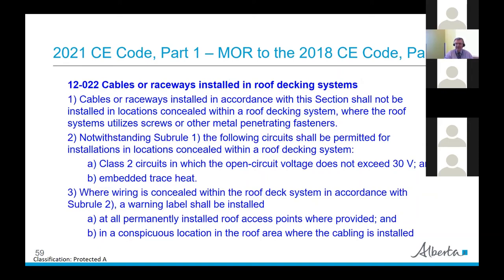There's also a new section on roof decking, addressing the problem of roofs being installed and drilling through conduits and wires. Cables or raceways installed in accordance with this section shall not be installed in locations concealed within a roof decking system where the roof system will utilize screws or other metal penetrating fasteners. Exceptions permit Class 2 circuits and embedded trace heating. Where wiring is concealed within the roof deck system per the exception, a warning label shall be installed.